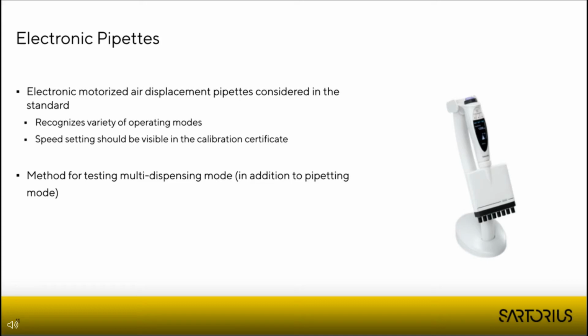A couple of highlights here. The speed setting for the electronic pipette can affect the results you get. Thus, the speed setting must be visible in the calibration certificate. So when you see a calibration certificate and you see that this pipette was tested at 150 and 10 microliters, you should also see the speed setting it was used with.